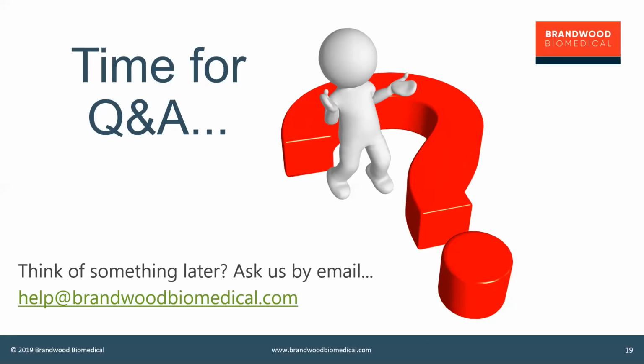What information is expected in a technical file for procedure packs where components are sourced from various suppliers and manufacturers? Oh, that's an excellent question, Danica. So as I alluded to earlier, more and more legal manufacturers of medical devices are outsourcing specific manufacturing processes. Now, that may be inline manufacturing, so maybe just a process step on your final device. It may actually be components that are put together into your device, or it could be components that go into a kit.